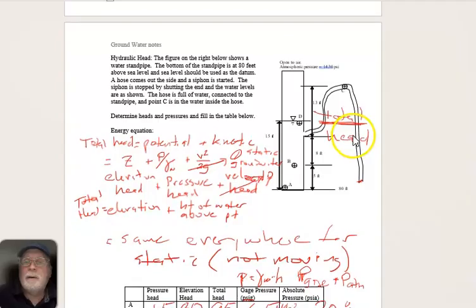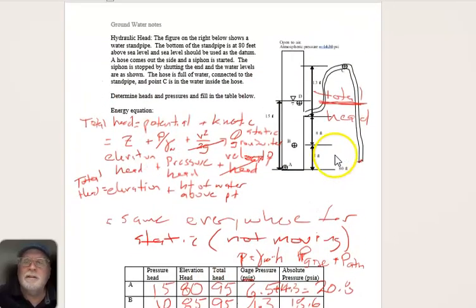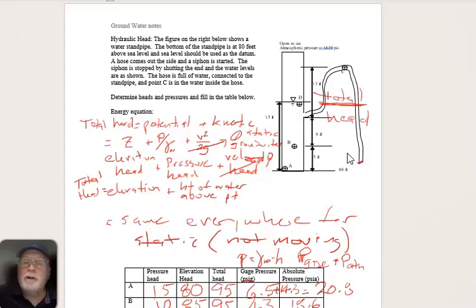That limit is about where the pressure goes to 0, so if I convert the 14.7 psi times 2.31, it's like 34 feet, minus the vapor pressure of water. So it's going to vaporize a little before that. So 30-ish feet is about how much you can suck water up, and it depends on the strength of your pipe or hose or whatever.